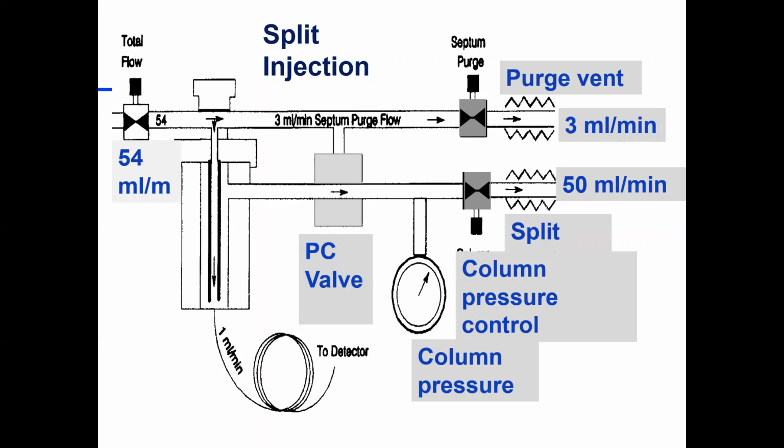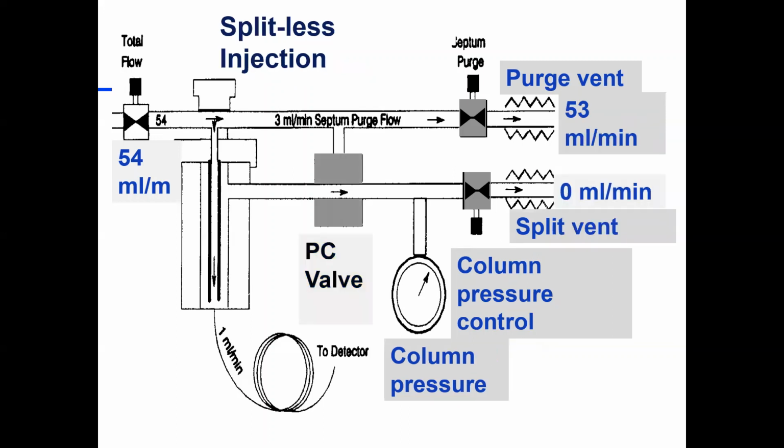So that's a little bit more of that injection port. And there are various controls. You can control your column pressure, control that split ratio. That's a 1:50 split, approximately. So 1/50th of your sample. I could go in with 20 mils per minute up here and have a 1:20 split. So you can see I can change my split ratio, how much gets dumped, vented, and how much actually goes into the instrument. And that's controlled somewhat by the concentration of our sample. Do we really need more material on our column, or don't we?